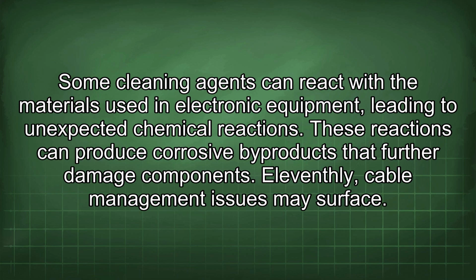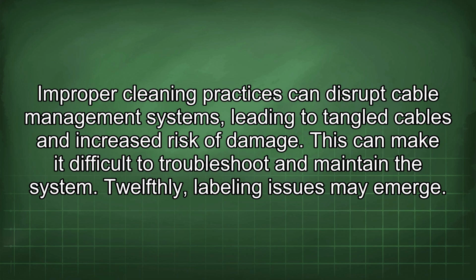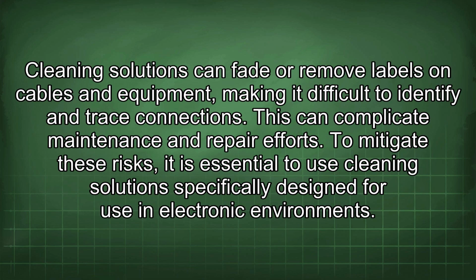11thly, cable management issues may surface. Improper cleaning practices can disrupt cable management systems, leading to tangled cables and increased risk of damage. This can make it difficult to troubleshoot and maintain the system. 12thly, labeling issues may emerge. Cleaning solutions can fade or remove labels on cables and equipment, making it difficult to identify and trace connections. This can complicate maintenance and repair efforts.